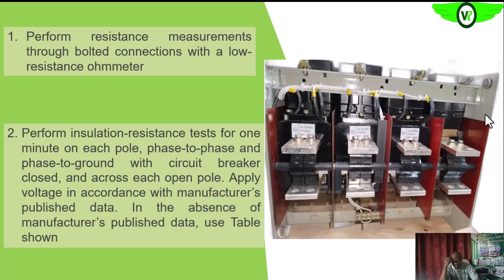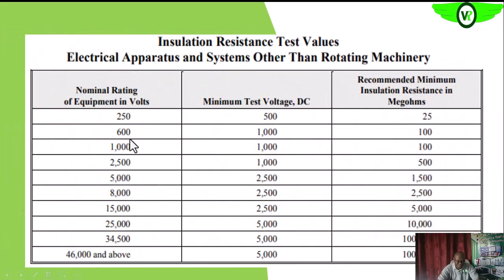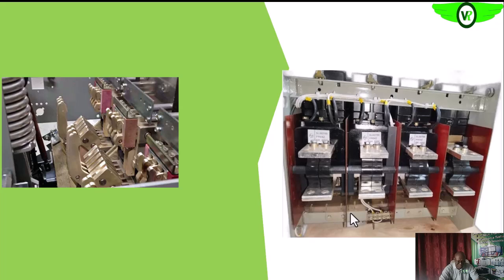If there is no specification for our facility, we can check what is recommended by the manufacturer of the particular circuit breaker, or else we can use this table. Since we are looking at medium voltage, between here and here is the nominal voltage. If we assume 11 kV, it is around here, so a 2.5 kV test voltage, that's 2500 volts, will be enough. Then we should expect a minimum of 5000 megohms. If it is less than 5000 megohms, we need to check what is making it so low, and if it is something we can improve, we improve it, either by drying out or by seeing what else we can do to improve the insulation.